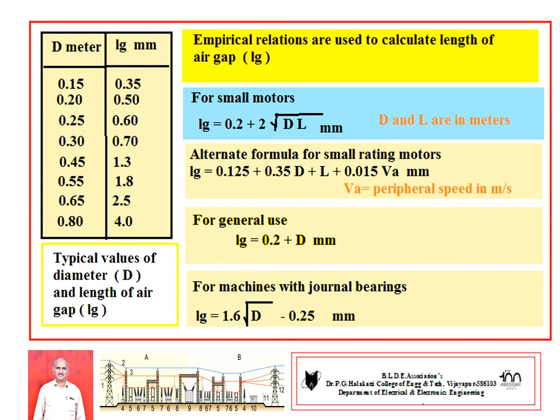In general use, Lg should be equal to 0.2 plus d, the answer is in millimeters, but we have to substitute the d value in meters. For machines with journal bearings, under such case Lg should be equal to 1.6 times the square root of d minus 0.25 mm. Lg should be in millimeters, again d should be in meters. These are some general empirical relations used to calculate the length of air gap. This value is very less. Remember, we have to substitute d and L values in meters, but the final Lg is in millimeters.